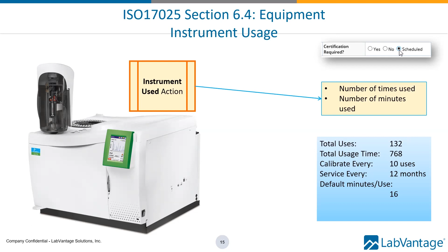Another nice feature of a LIMS is the ability to track the usage of specific pieces of equipment. Doing so may let you choose to do calibration or service events based on a certain number of uses rather than, say, 5 weeks or months or some other time period. If you've purchased the equipment with a grant, it also helps you to justify the value brought by the instrument that grant provided. Knowing the usage can also help you justify the purchase of additional equipment if you find that the equipment is being heavily utilized.